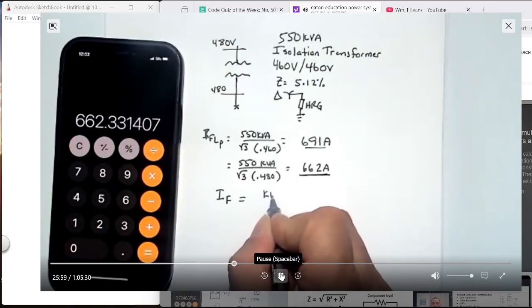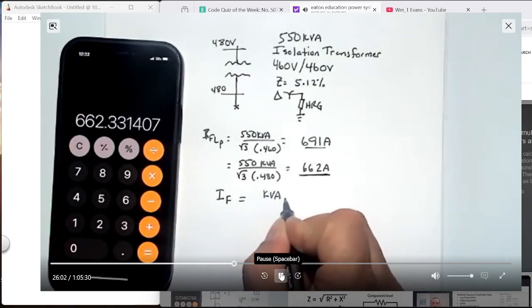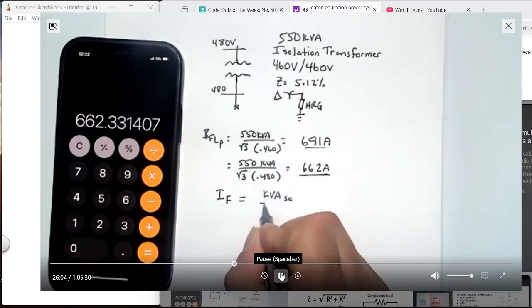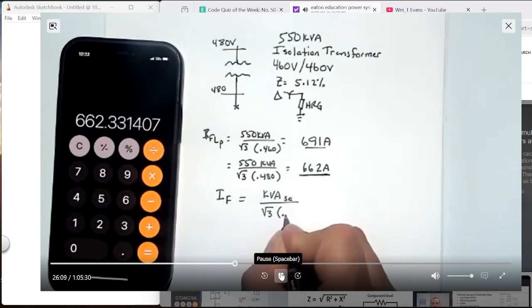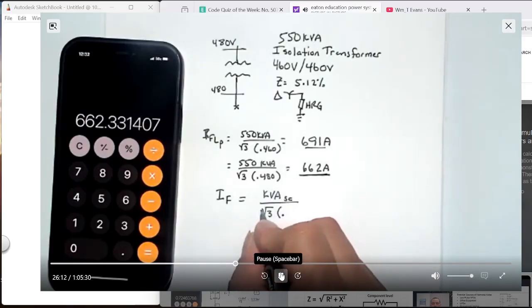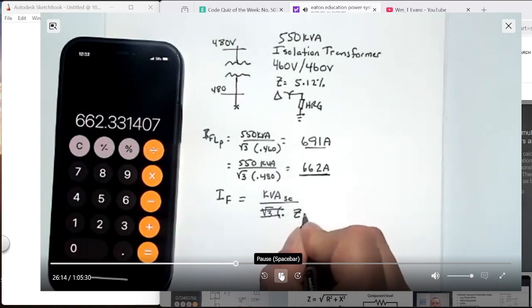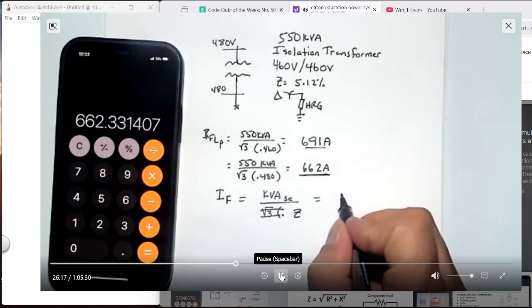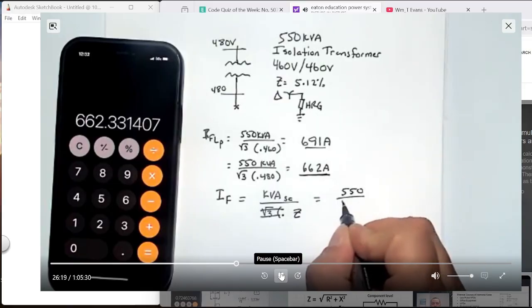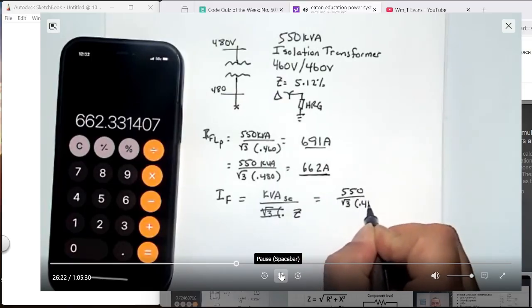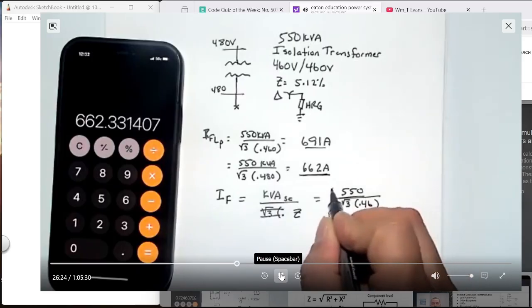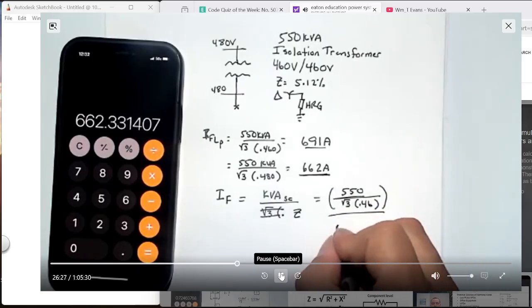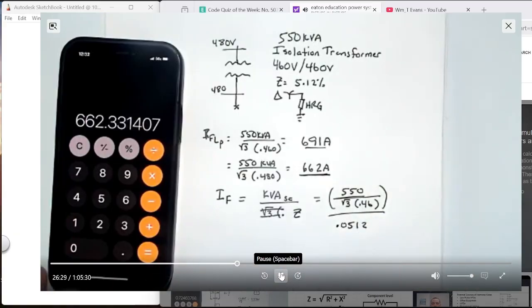Now for the fault current, I'm going to use the short circuit kVA for this one. The reason I'm going to use the short circuit kVA is because that's based on the rating. And then the kV line, we're going to divide that by the impedance. So we're going to do 550 divided by the square root of 3 times 0.46. And then that's our short circuit kVA divided by our impedance, which is 0.0512. So we get 550 divided by that. That's going to be that number.